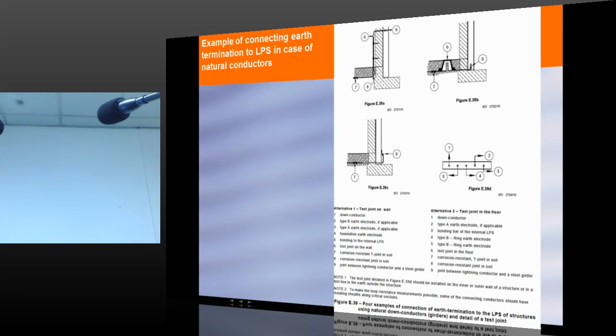So this is an example of connecting earth termination to the lightning protection system in the case of a natural conductor. That means, in case of using the steel reinforcement, how to connect the structural steel with an outside soil equipotentialization. There are certain conditions given. The conditions are explained here, but for each condition there is an explanation which also needs to be considered.